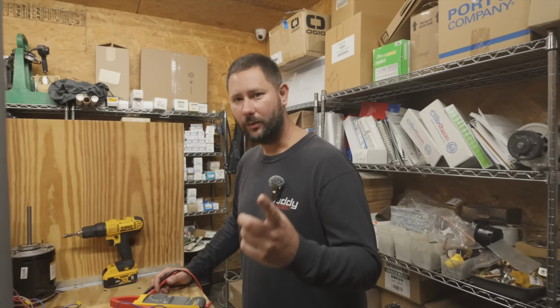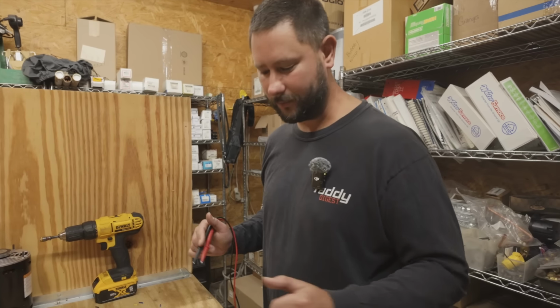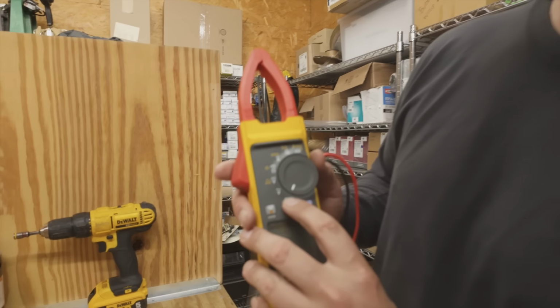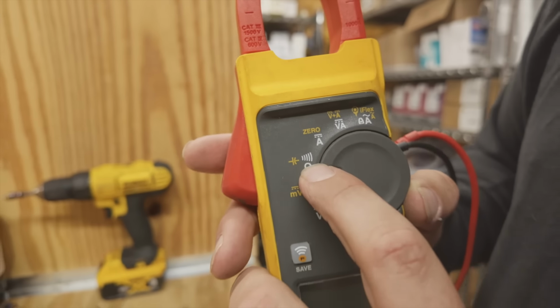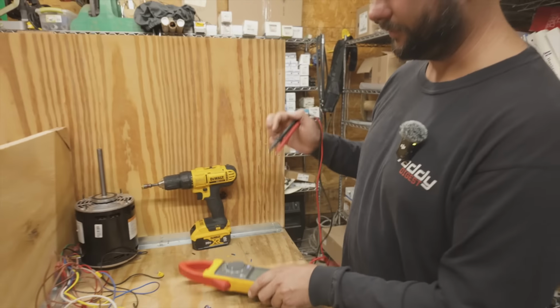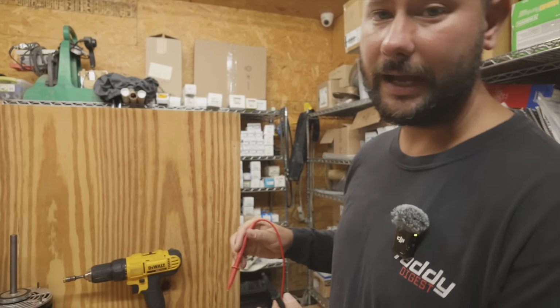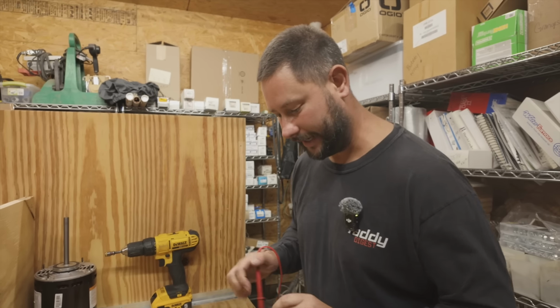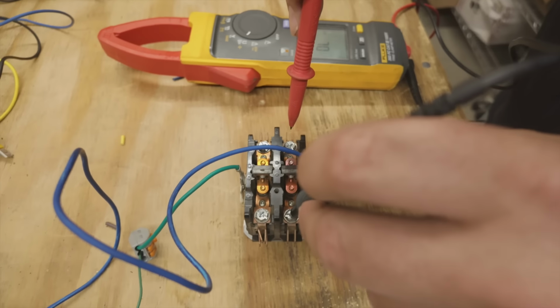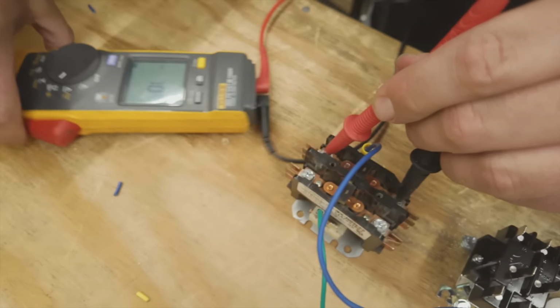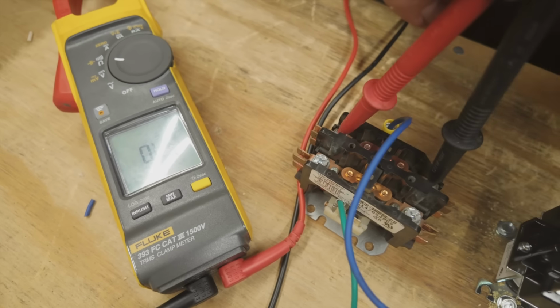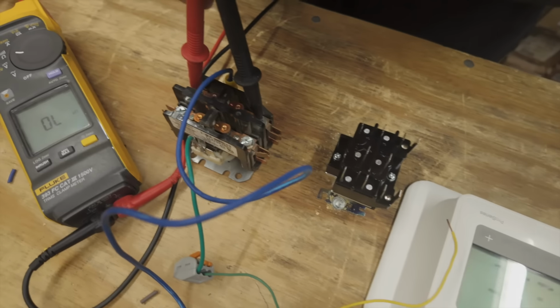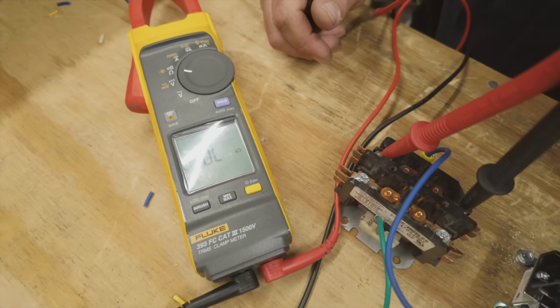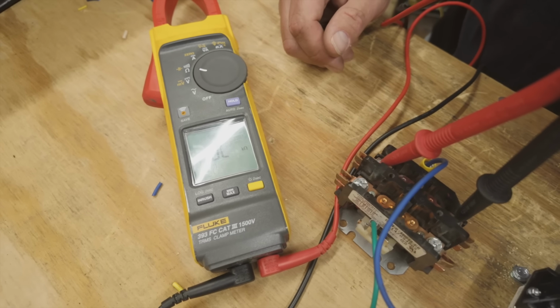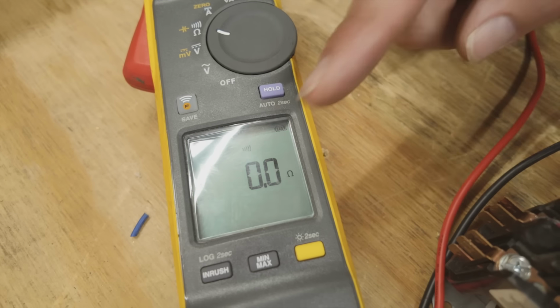Let's go to a switching relay. I want to show you one more check using the meter for this contactor before we move forward to that switching relay. So I'm going to take my meter dial and put it on continuity right here, same dial as ohms. Whenever we touch our meter leads together, it's going to beep, indicating that we have a closed circuit. So right now, if I check from one side of the contactor to the other, it doesn't beep. You can see the meter says OL. But whenever I hit fan on, because we've wired it now to the G terminal, the contactor pulls in and we completed the circuit. Just want to show you.